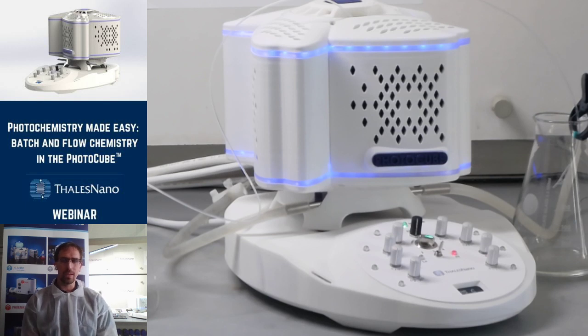I'm not sure what kind of volume you are talking about, so I will split my answer into two bits. The first one is for batch reactions. The reaction chamber is a 7 times 7 times 7 centimeter cube shape, so in principle, that limits the maximum volume. With our current standard holders, the biggest ones can fit vials with a 30 milliliter internal volume. If you go into flow, our loop sizes range between 2 and 20 milliliters. But obviously, because we are talking about a continuous flow procedure, you can push much higher volumes through the instrument as well.